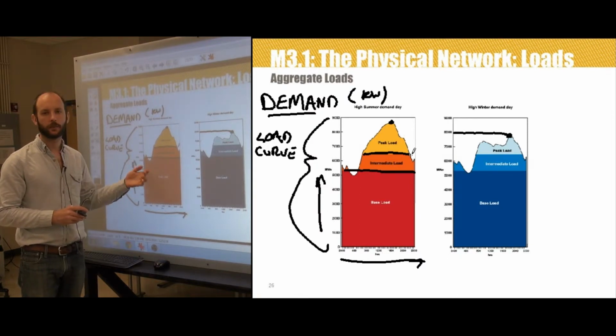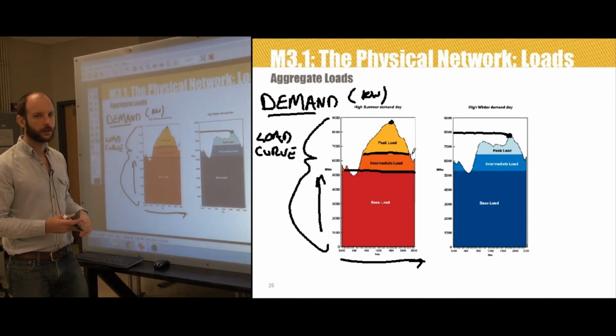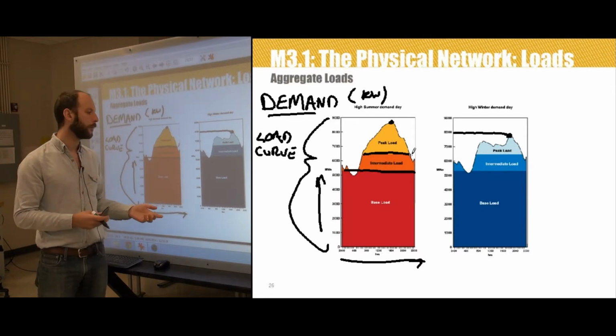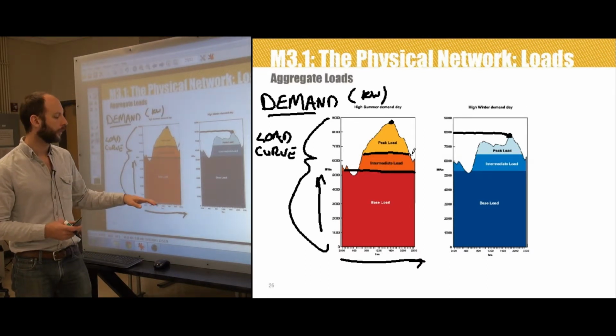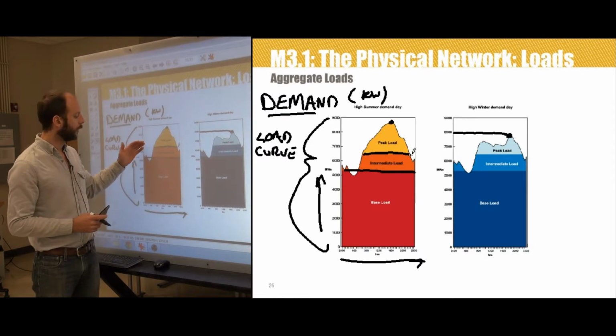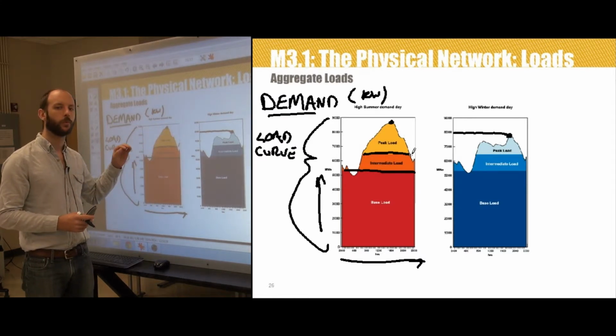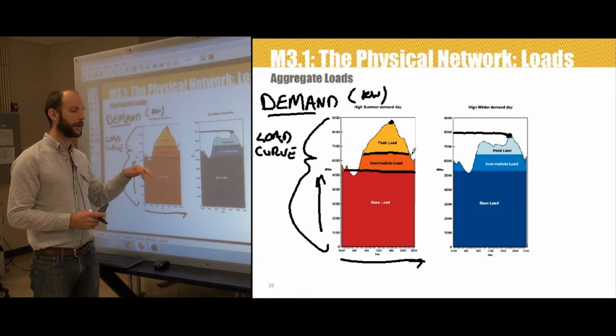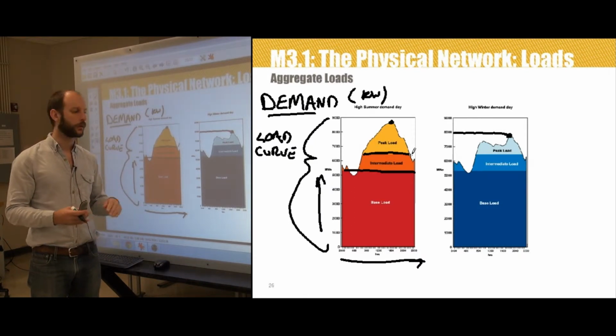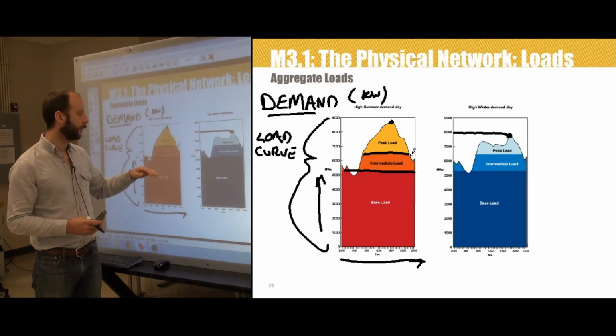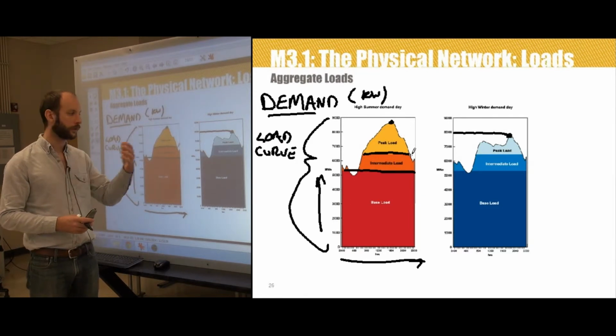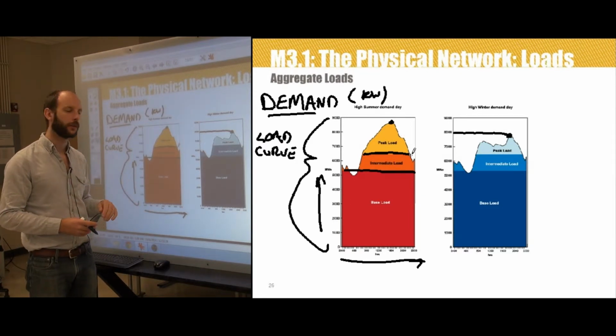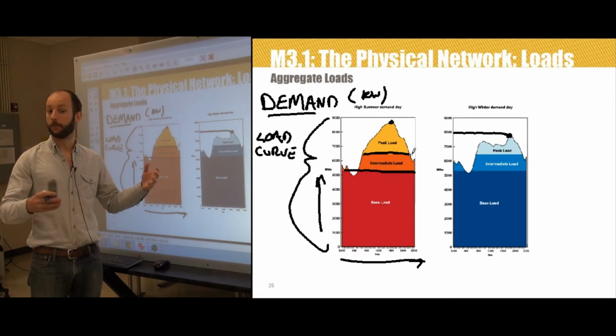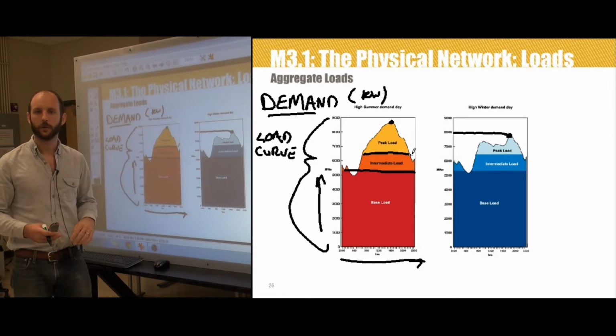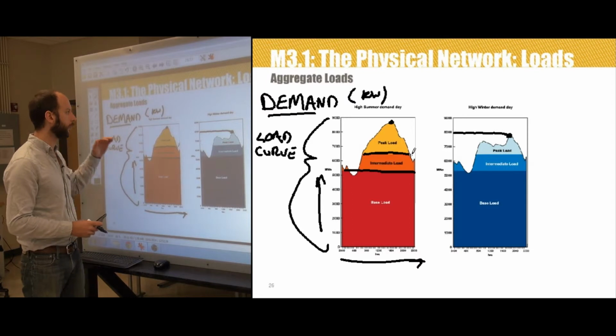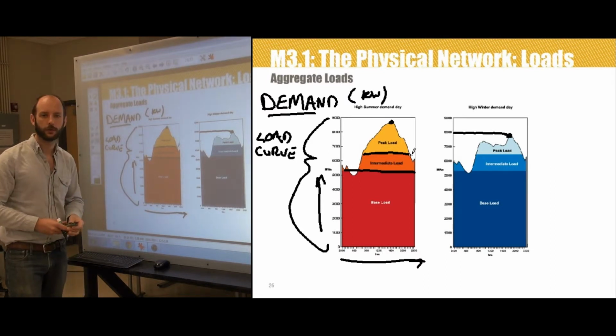Curves like this can be drawn using data for a single day, data averaged over a week, over a month, over a year. Really the purpose of charts like this is to show the time-dependent behavior of when electrical loads demand power for a certain utility, so that you can plan your generation during the different times of the year. You need to make sure you have enough coal, that you've got the contracts in place to purchase the fuels, and that you have big enough generators to meet the predicted load. So very important, the ideas of demand and load curves.